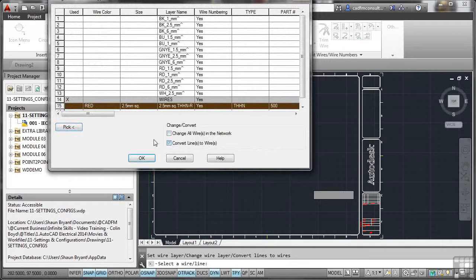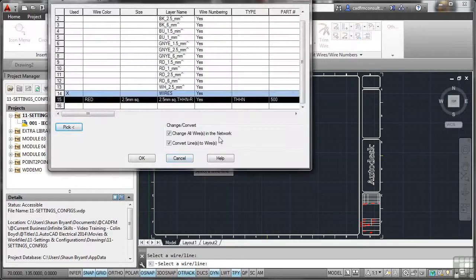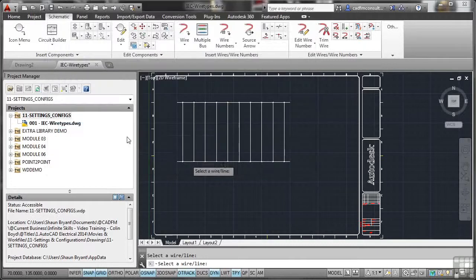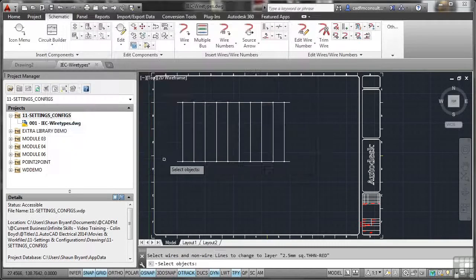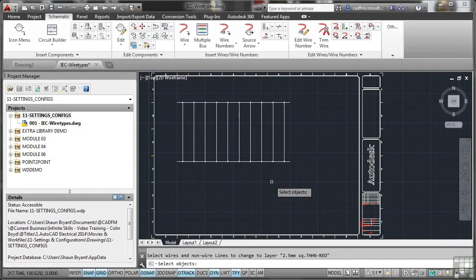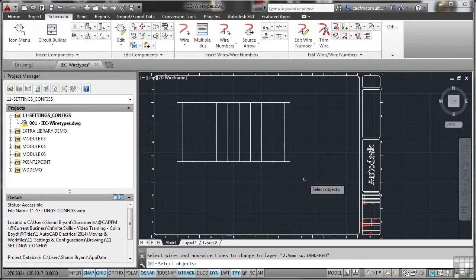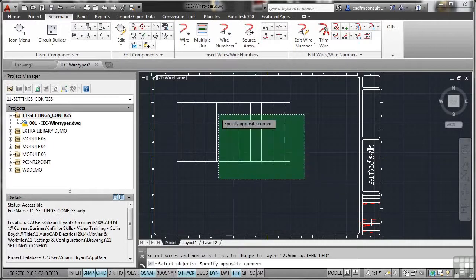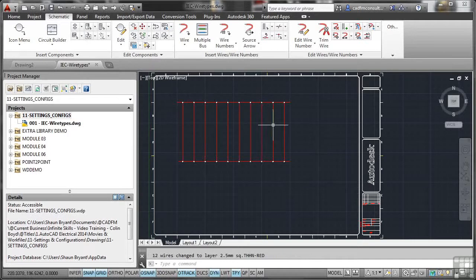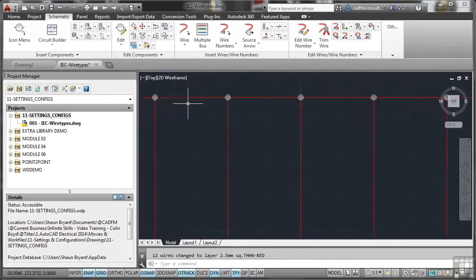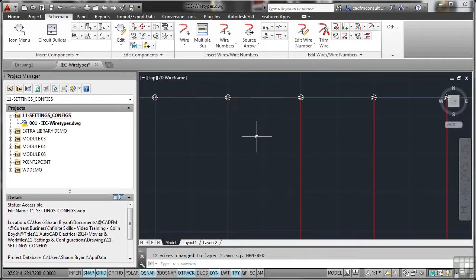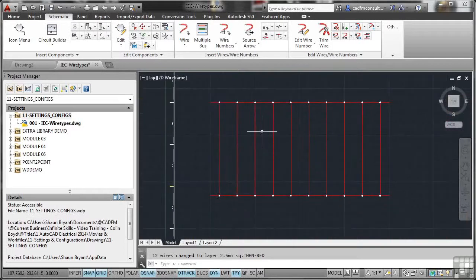Make sure you pick like so and then pick each one. If you go pick there and it says 'select a wire or line,' you can select it and OK it. What you've done is told AutoCAD which wire type you need to change, and now it's prompted you to select the objects. On the command line it says 'select wires and non-wire lines to change.' Select all of them, press Enter to finish, and they update. Notice it only picks out the wire lines — the connectors on the ladder stay on their own layer, which is symbols. Very clever stuff, these smart lines. Make sure you use them in your AutoCAD Electrical projects.